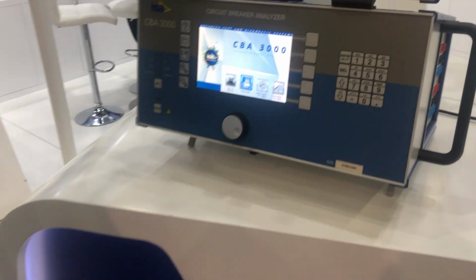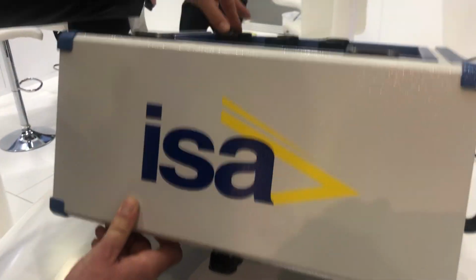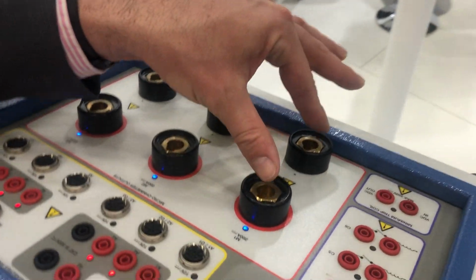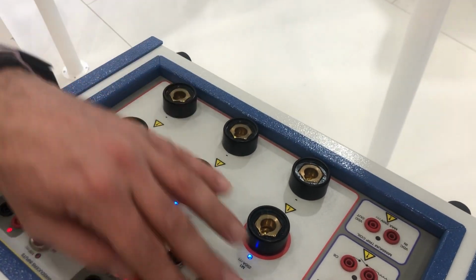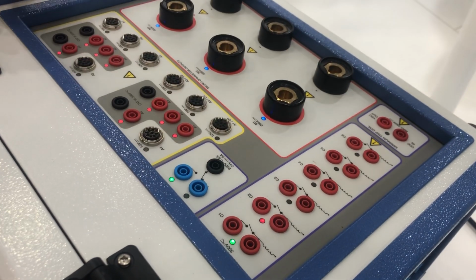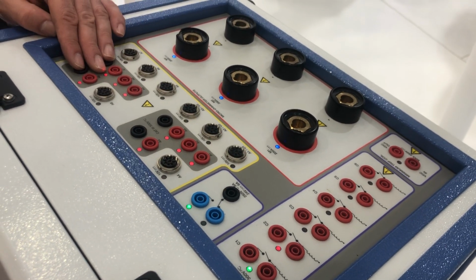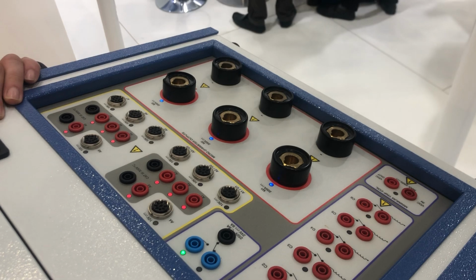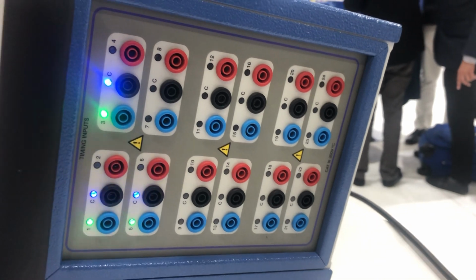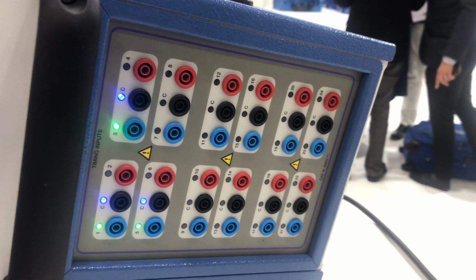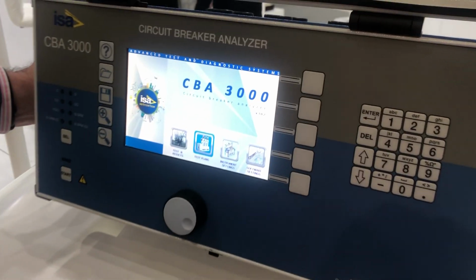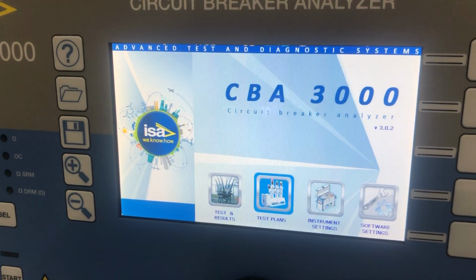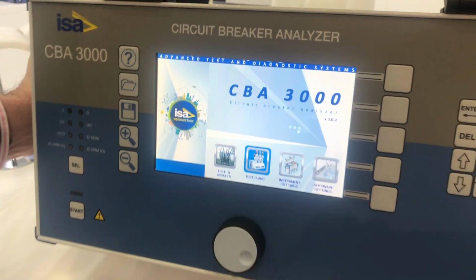And there is another circuit breaker tester, which is a CBA3000 from ISA. This device has the ability to generate DC current up to 200 amps, 3-phase. We can have 2, 4, or 6 commands, and there are many analog inputs to measure the voltage drop as well as the minimum tripping coil. On the side, you can see the contacts, which can be main or auxiliary, and in general, the device comes with all the cables and boxes as well as the CT8000. So these would be the circuit breaker analyzers.